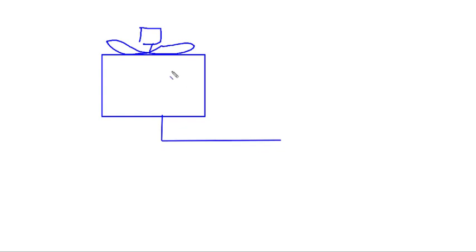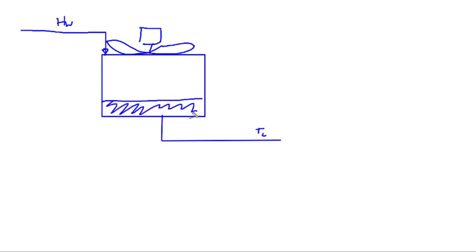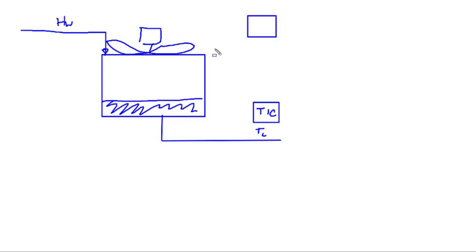You have the outputs going out to the plant and your input coming in here. You've got your hot water and your cold cooling water going into the plant. This is a sump normal level control. They put a TIC block here to control temperature, and then they put another PID block up here which controls the speed of the machine.